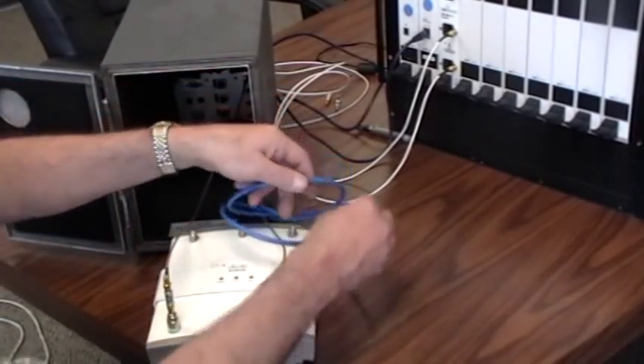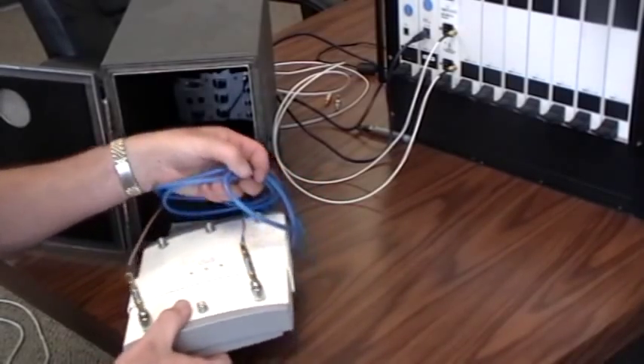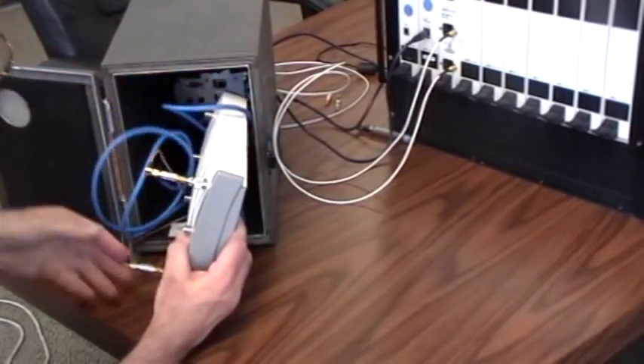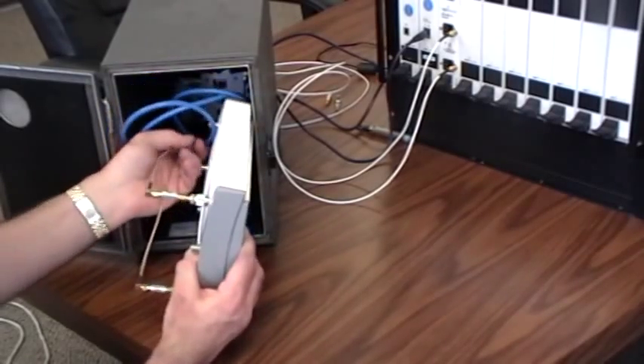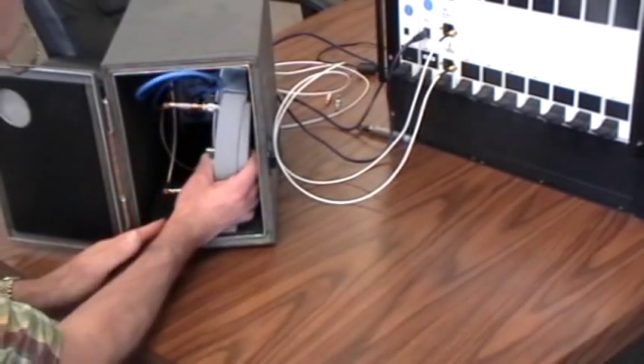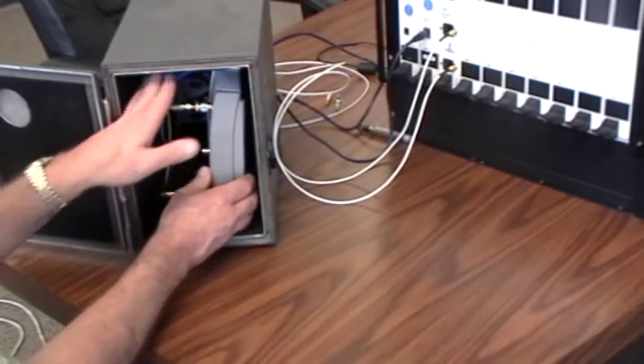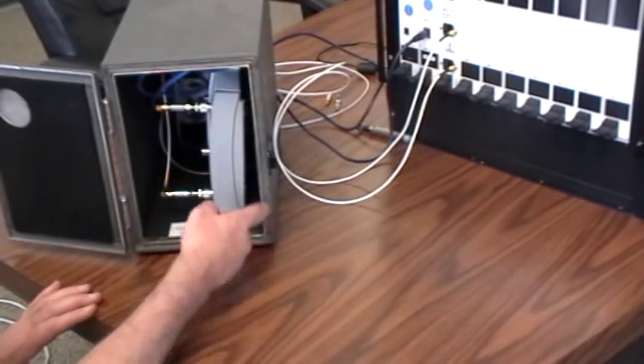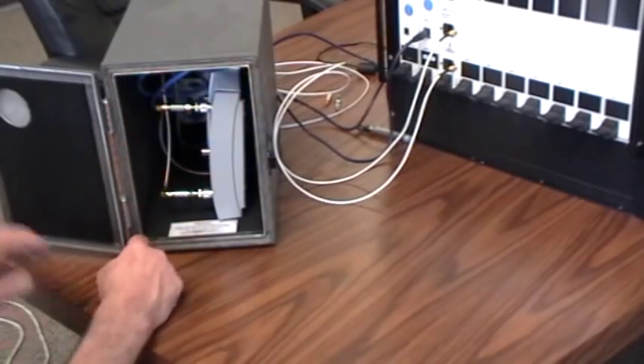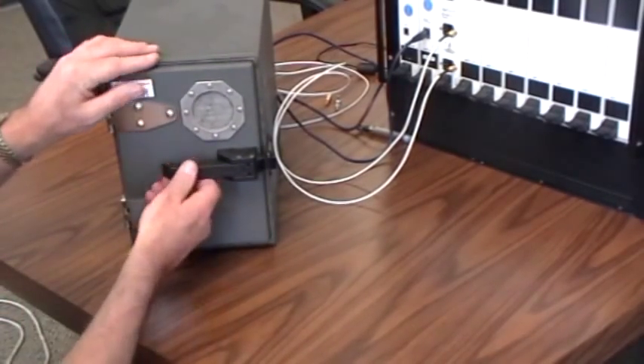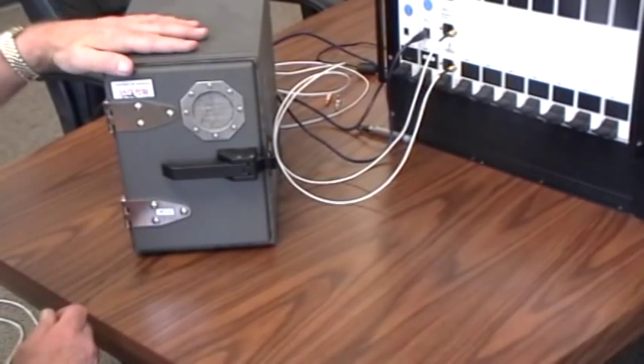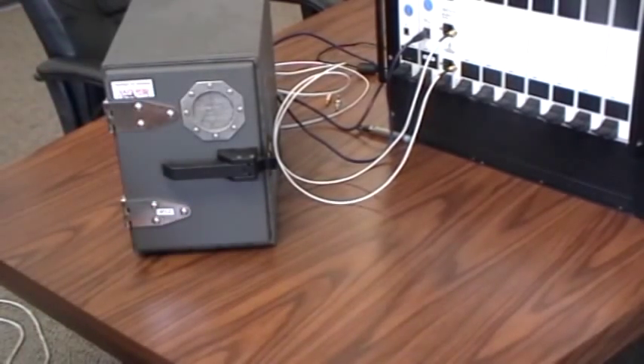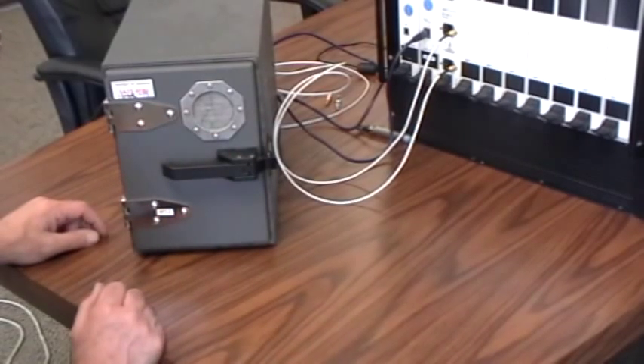Now your job is to gently place the access point inside the enclosure in such a way where you're making sure that the cables don't kink and they have gentle bends. We've got everything inside the enclosure. We don't want any cables to close in the seal. When we close the door, we've got plenty of RF isolation between this access point and anything else in the lab, and we're able to make our measurements.